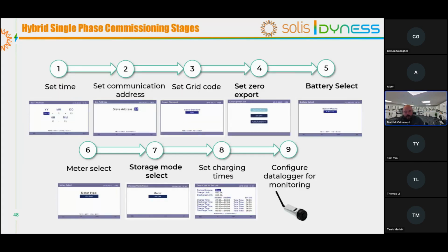Actually, in terms of the commissioning side of it, as we said, it's kind of as plug and play as possibly can be. So once you have the inverter set up and you have the battery selected properly, then you shouldn't necessarily have to change too much afterwards. There might be a few additional things that I'll talk to you in a minute about, but ultimately you have to set the time and the address, set the time in terms of the date and the time, and that's hugely important.